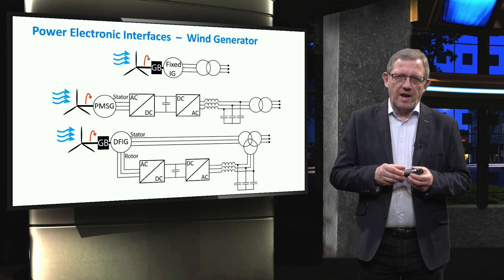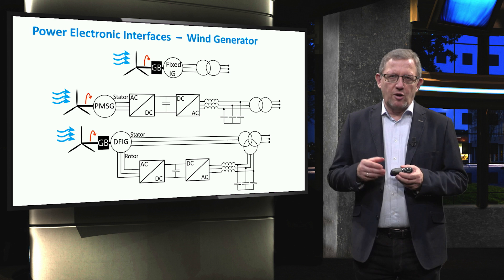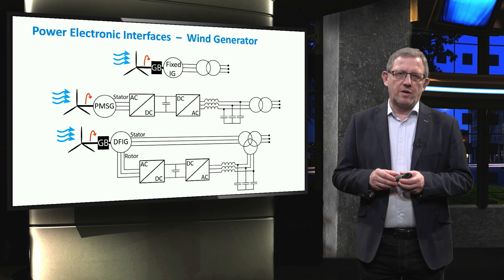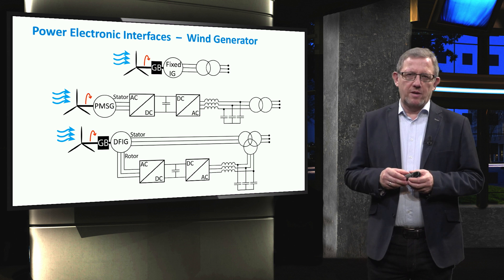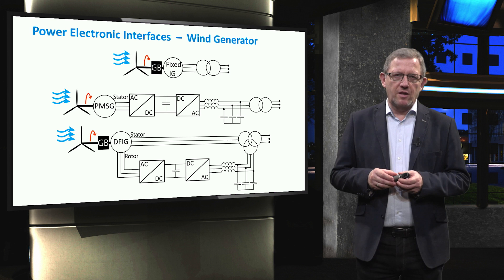On the other hand, the stator of the doubly-fed induction generator wind turbine is directly connected to the electrical grid, while the rotor is connected through a power converter. The size of the power converter is about one-third of the rated power. Unlike a full-scale permanent magnet synchronous generator, the doubly-fed induction generator still needs a gearbox.